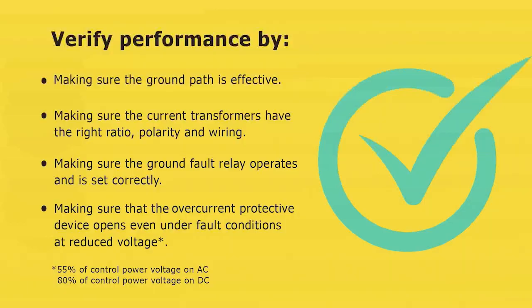Hey, let me jump in here with some field advice. This happens almost every time. The ground fault protection system typically ships at the minimum settings. If you don't do something to make sure that it works properly, it's set properly, and that the polarities are right, you can have a lot of problems. We see it almost every time, some issue with the ground fault system after it's been installed.